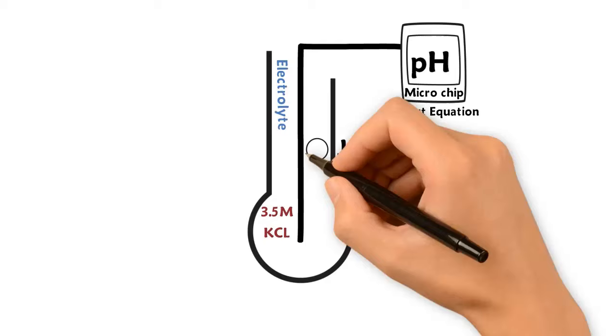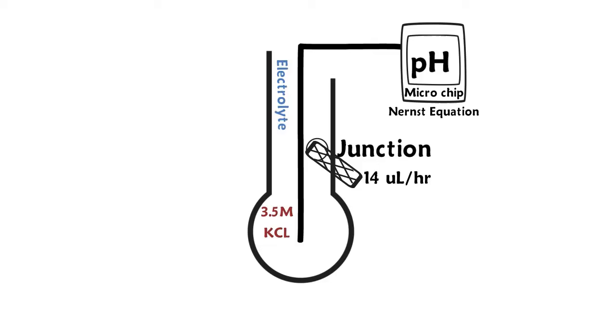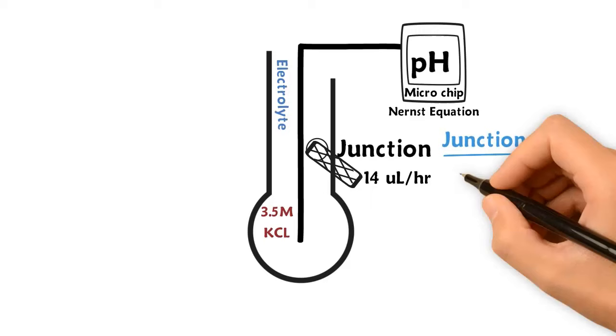Cloth junction equals 14 microliters per hour. There are three basic types of junctions to allow for the leaking of the electrolyte KCL solution into your testing solution.